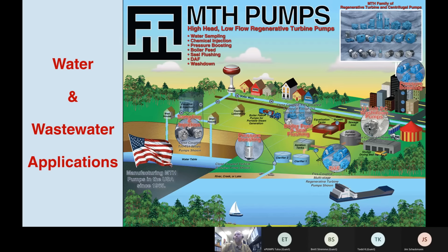And then the other one is dissolved air flotation. And Regen turbines are very good at taking and introducing air into the inlet side of a Regen turbine, and they can handle 20% vapor. And what happens is the Regen turbine impeller itself will take the air and it mixes it with the water and it makes the air into a microbubble. And that microbubble will then go into a trough of sorts that has wastewater in it that will grab onto particles in that water and make them float to the top where they can be skimmed off, and you can clean that water for either reuse or recycle.